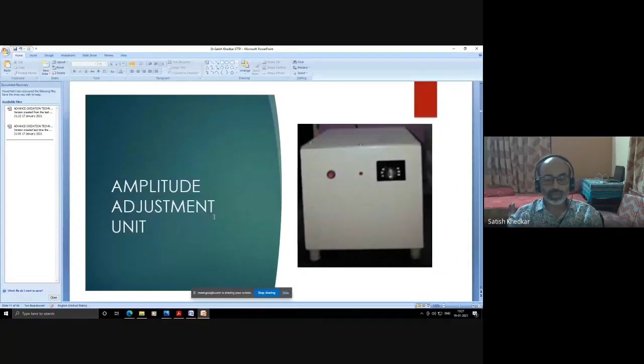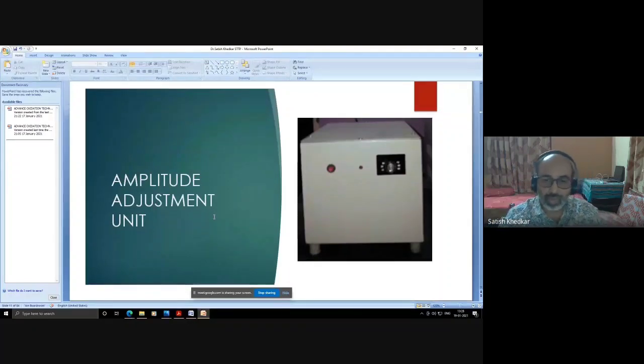So the amplitude is responsible for the transmission of power into the liquid being cavitated. At lower amplitudes, you will have lower energy being transmitted into the cavitation liquid. At higher amplitudes, you will find that a higher amount of energy is transmitted into the liquid being cavitated. So the energy transferred into the liquid being cavitated depends upon the amplitude at which the equipment is set. If you want a higher transfer rate, then the amplitude should be towards the higher side. If you want a lower transfer rate, then the amplitude should be towards the lower side.